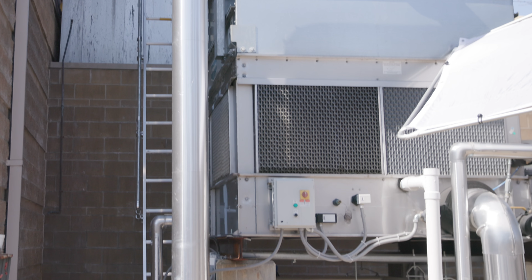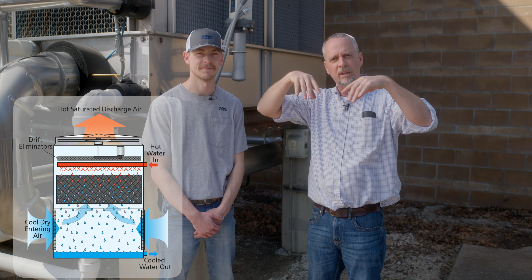So the easiest way for me to get it in my brain to understand it is, in any cooling tower, we're taking the warm process water from whatever we're doing in the building, whether it be a chiller or water source heat pumps. We need to cool that water off in the cooling tower. So you pump that water up to the very top of the tower, and then it's distributed through nozzles over some cooling tower fill, and it trickles down.